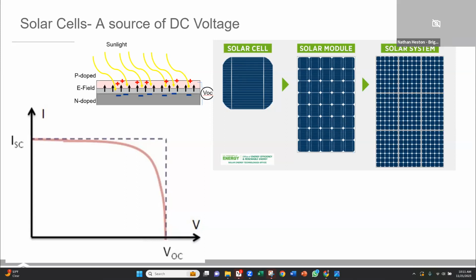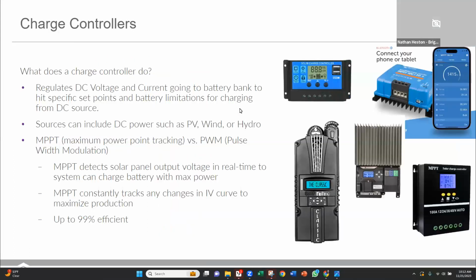It increases the open circuit voltage with temperature, and the short circuit current can go up as well. And then higher temperatures lead to lower voltages and affect the current too. So we're going to talk just a little bit about charge controller equipment. This equipment is designed to stay at that maximum power point of the solar modules of that solar array. There's different types of charge controllers. They all do basically the same thing, try to sit on the knee of that IV curve, producing the most amount possible.